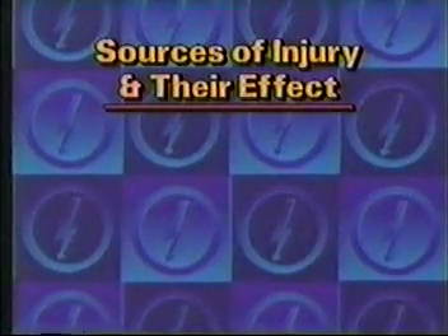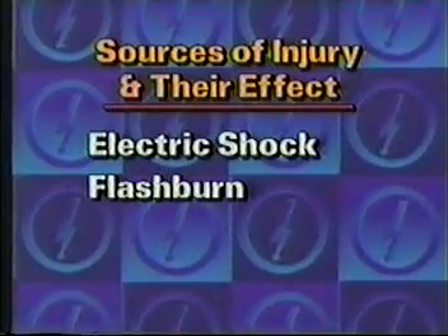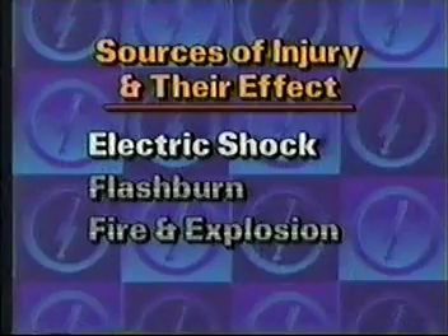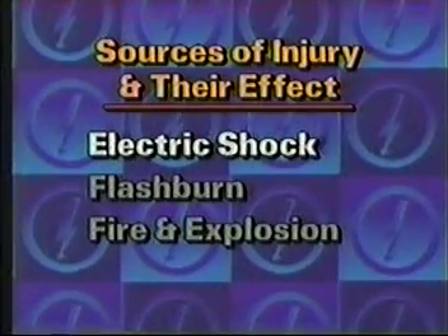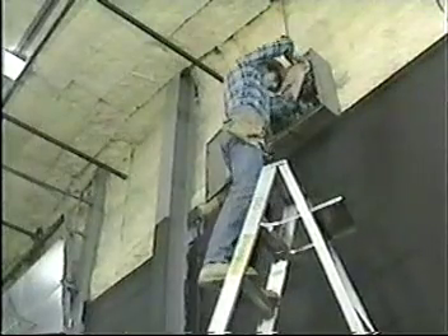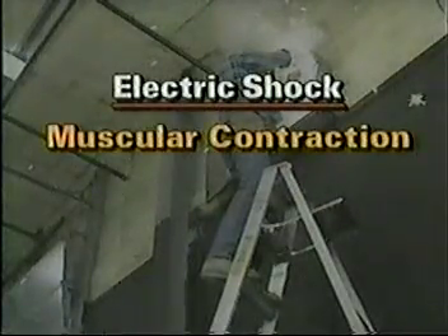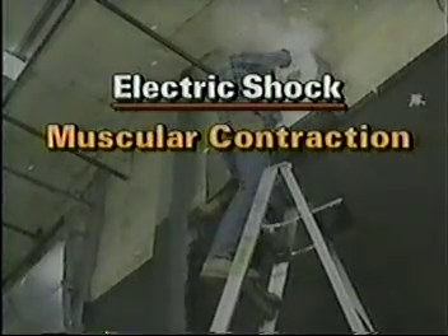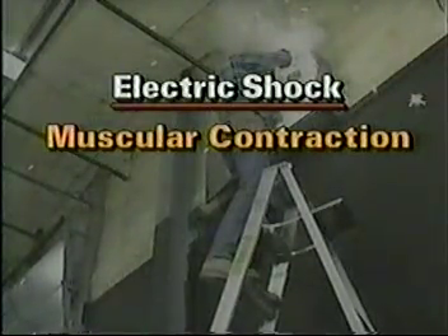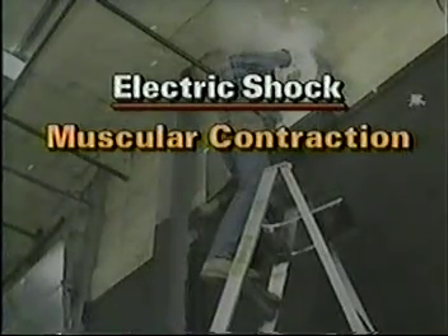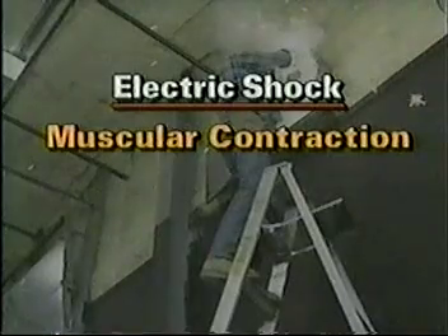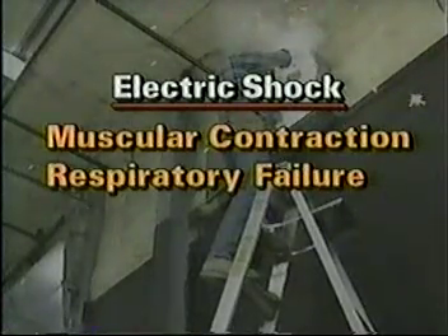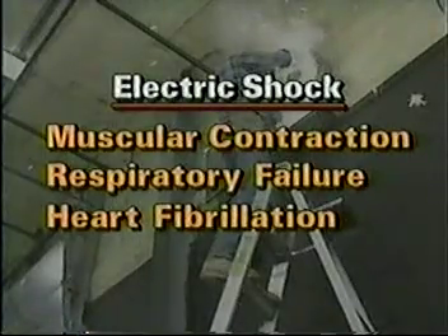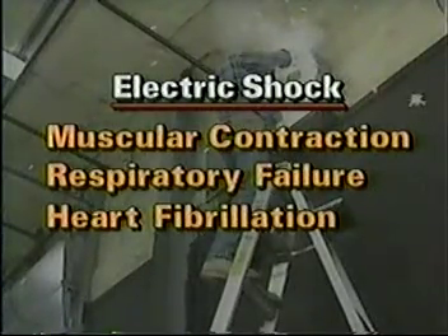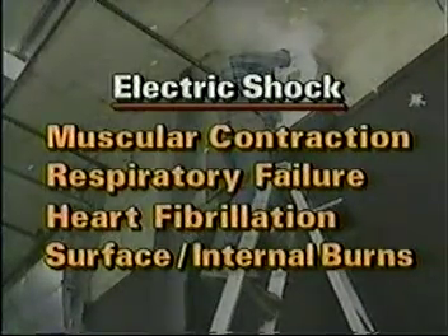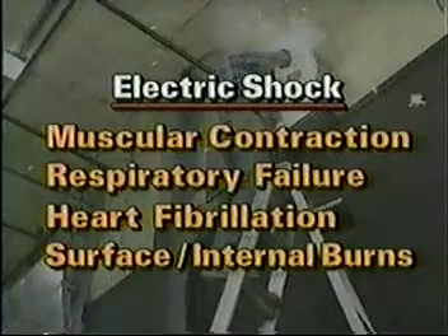They can be subdivided into 3 categories: electric shock, flash burn, and fire and explosion. Shock effects can range from a minor irritation to cardiac arrest. The most common symptoms of electrical shock are muscular control failure or contraction. This often causes the victim to grasp and be unable to release the source of the shock. Muscular contractions can also lead to other problems, such as falling from an elevated work position. Other effects include respiratory failure, heart fibrillation, that is the cessation of the rhythmic pumping action of the heart, and severe surface or deep internal tissue burns from the heat generated by the current flow.